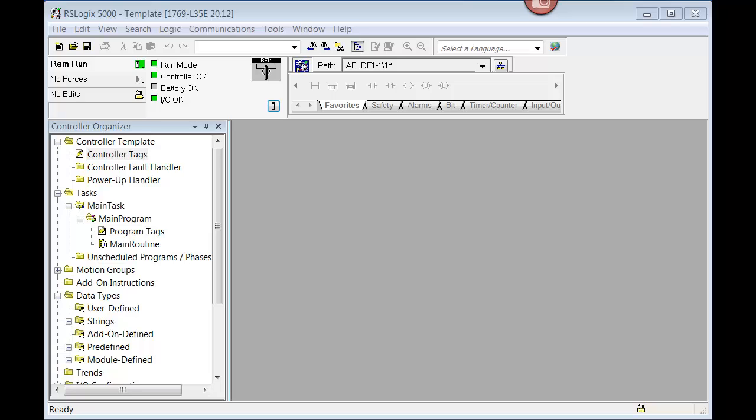So here are those 6 single element arrays, and it's in your lab manual, and it shows B3, T4, C5, R6, N7, F8. And then we expanded B3 out to 10 elements. And we reminded you that you could expand it out as far as 256 elements. We're not going to repeat the graphic in the video here. The next section was how SLC500 data files look as single element arrays in the Logix Engine. So we go to program tags right here, because remember that those single element arrays were in the program tags for the SLC500, PLC5, Micrologix platform.